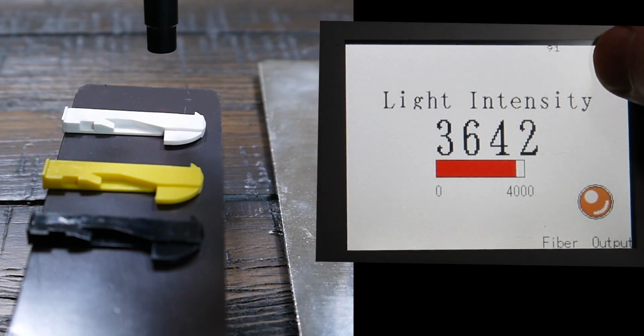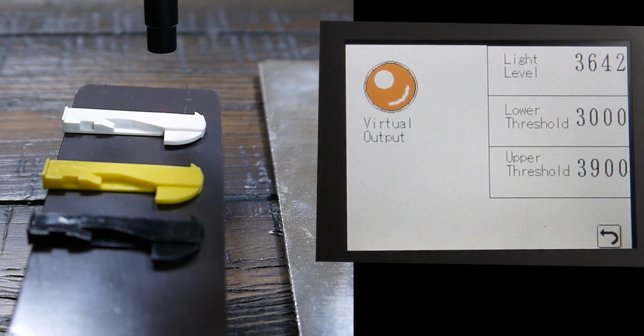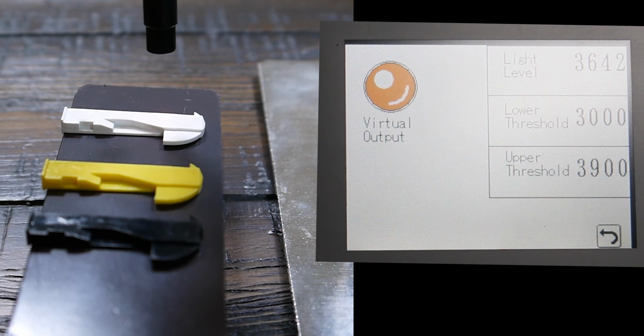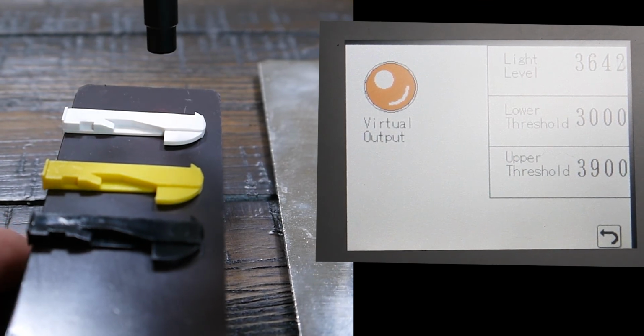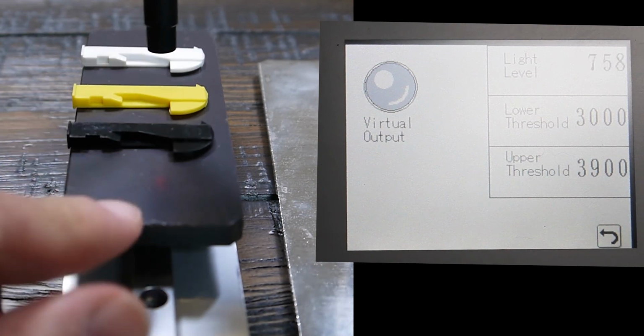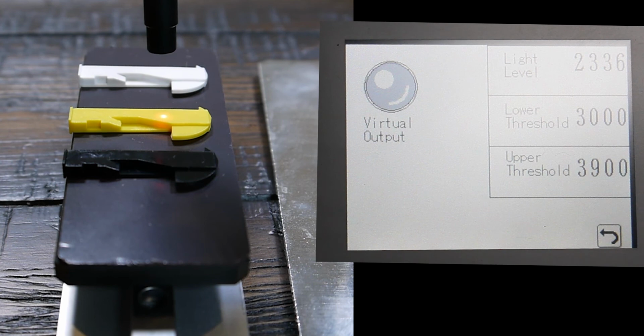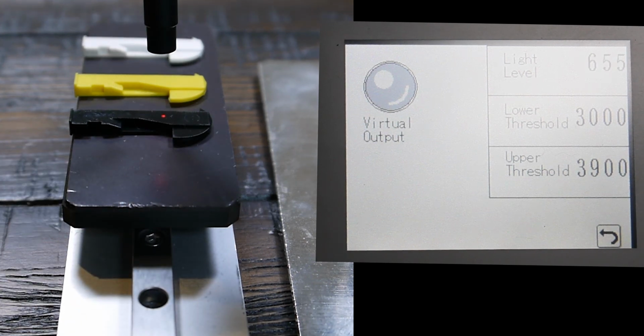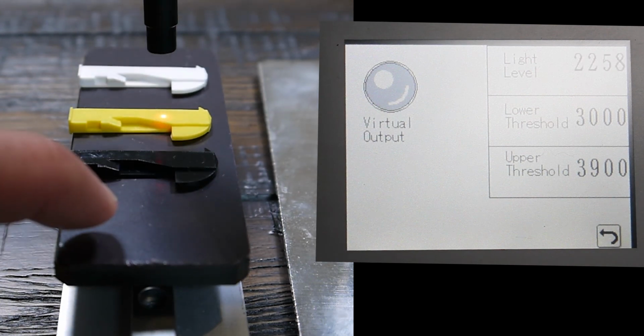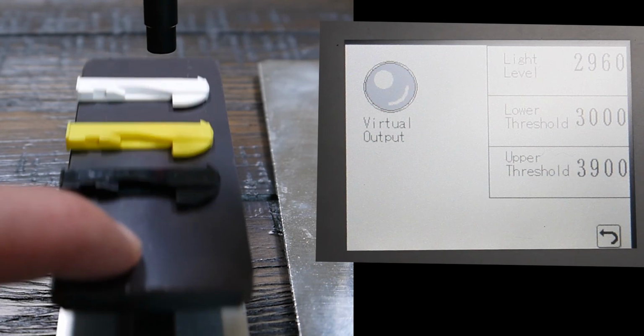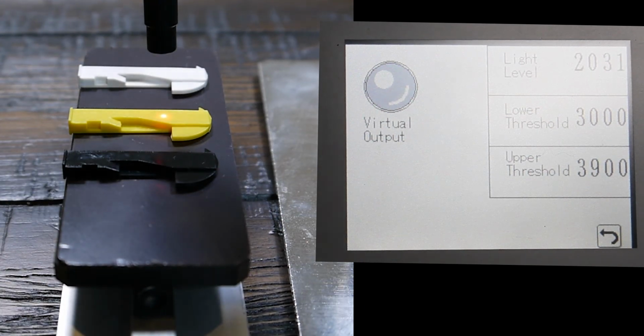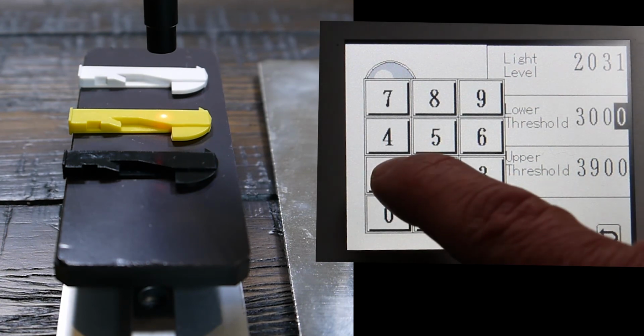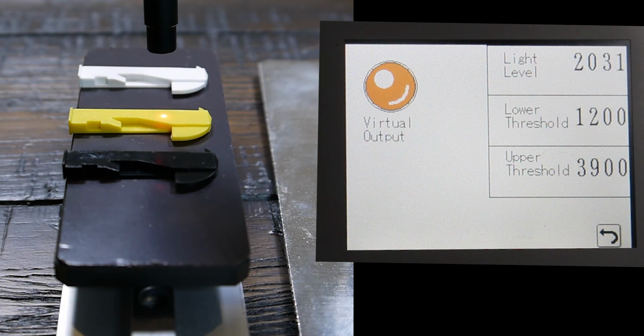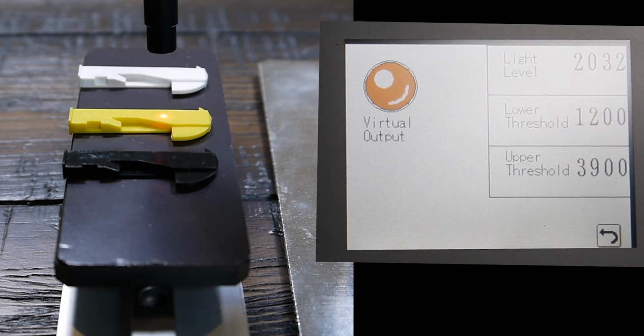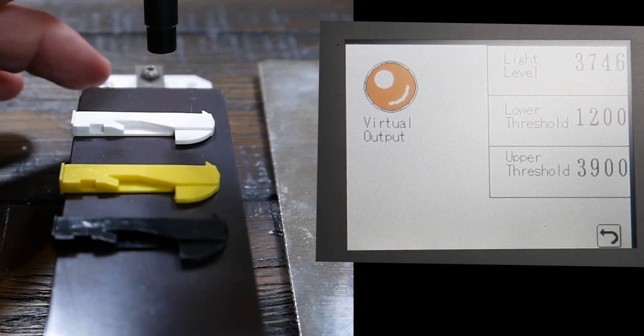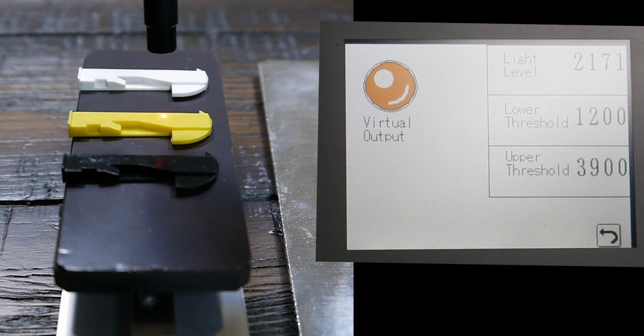Okay, so we're going to go to this screen here, and we're looking at the white part, and you can see the incident light level is around 3600. On the yellow part, it's 2300. And on the black part, it's around 655. Okay. So on the lower threshold level, we'll put that around 1200. And then for the upper threshold, we'll put that around 3000.